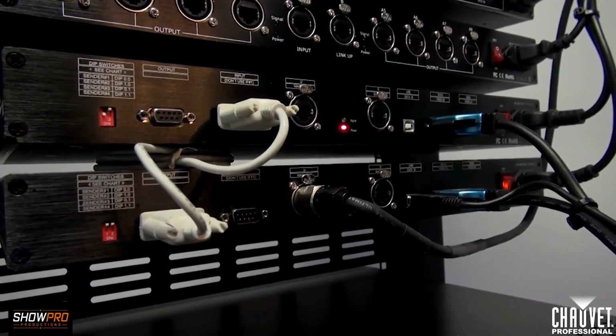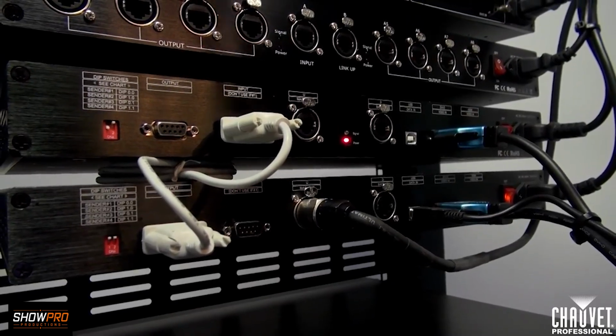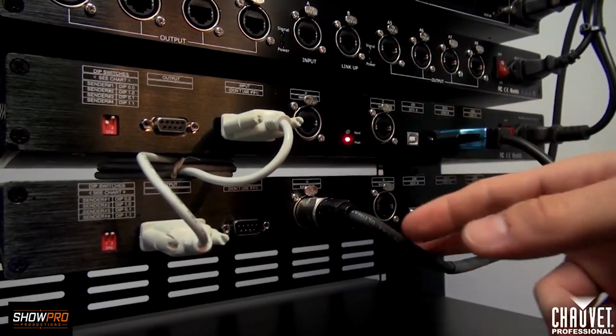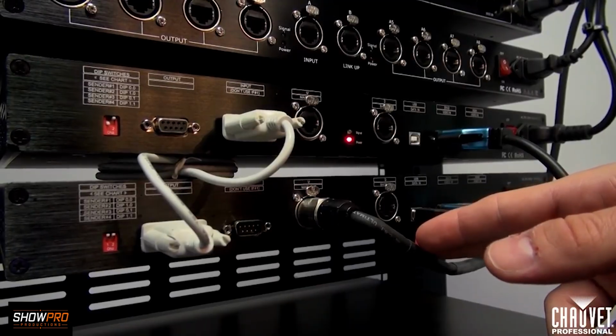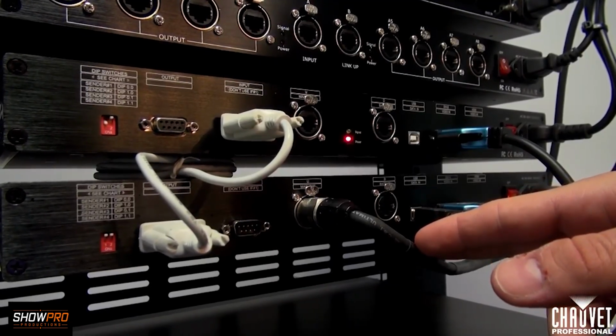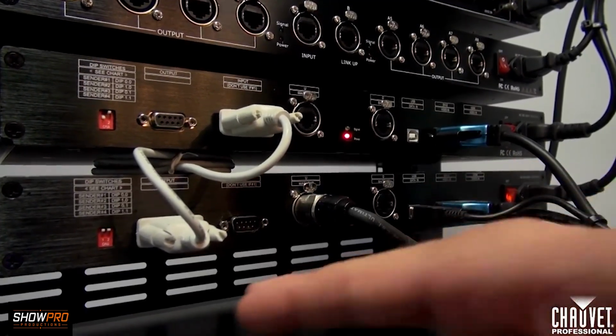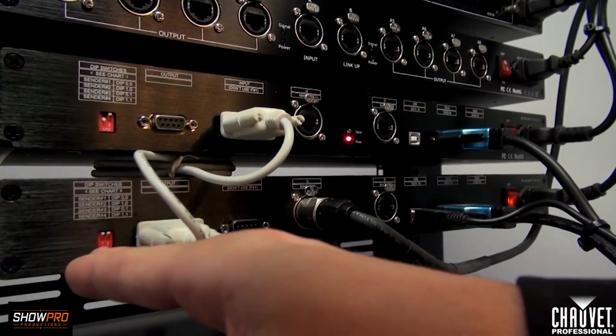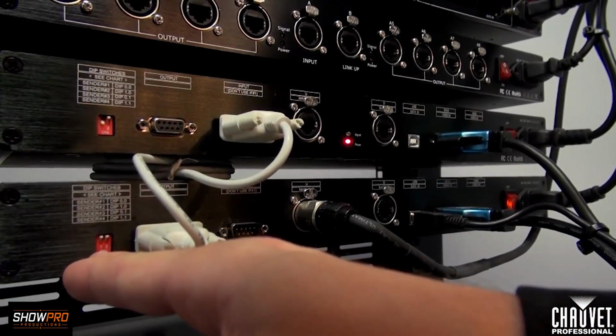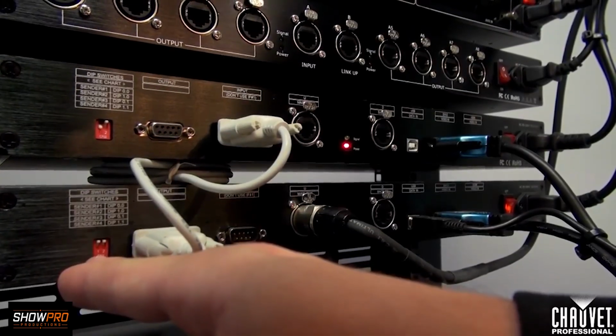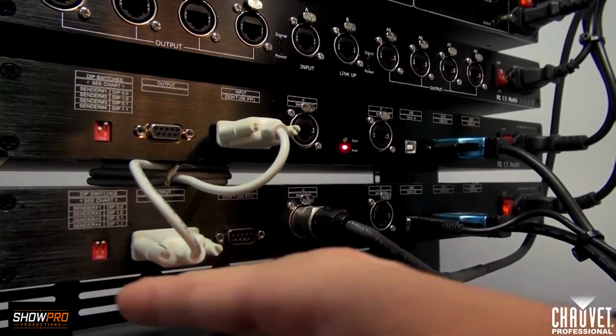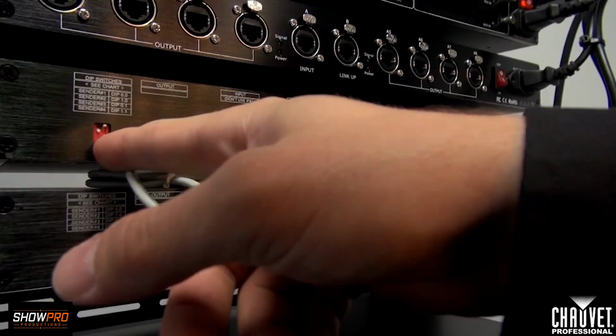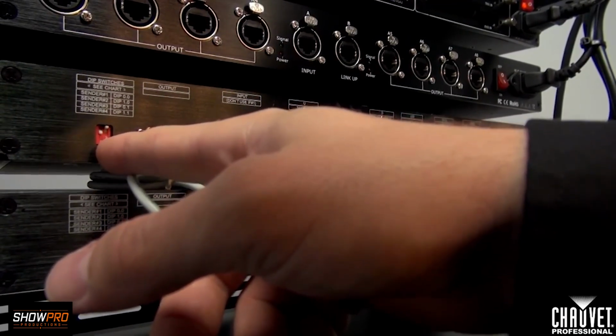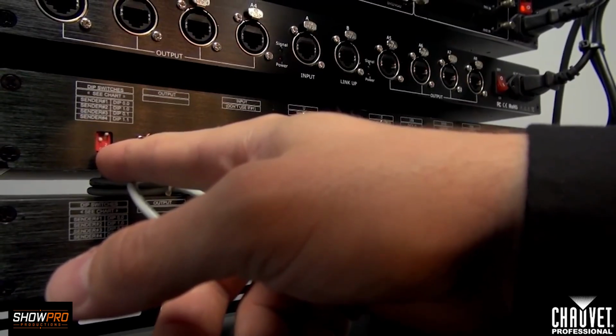First, I want to introduce the VIP driver. We have two VIP drivers in this setup, connected in cascade function. On the left, the dip switches are both set up, defining this VIP driver as number 1. On the one above it, the dip switches are set 1 to on, 2 to off, defining this VIP driver as number 2.